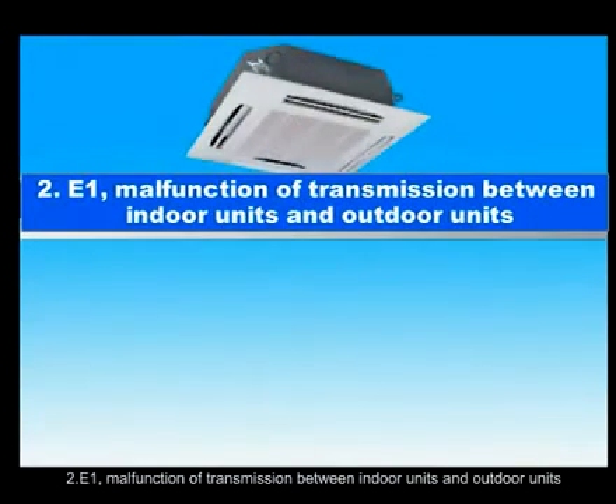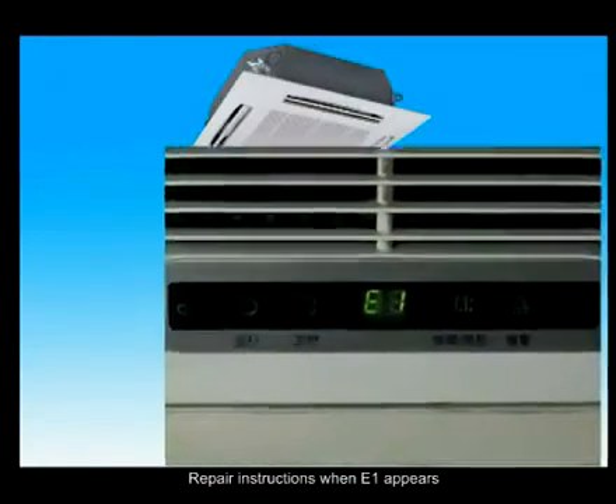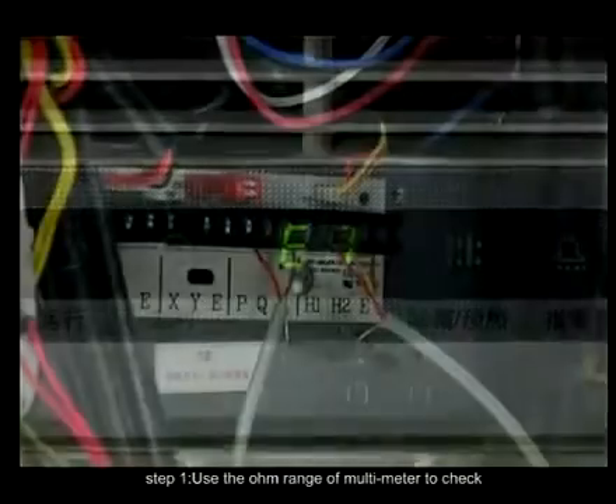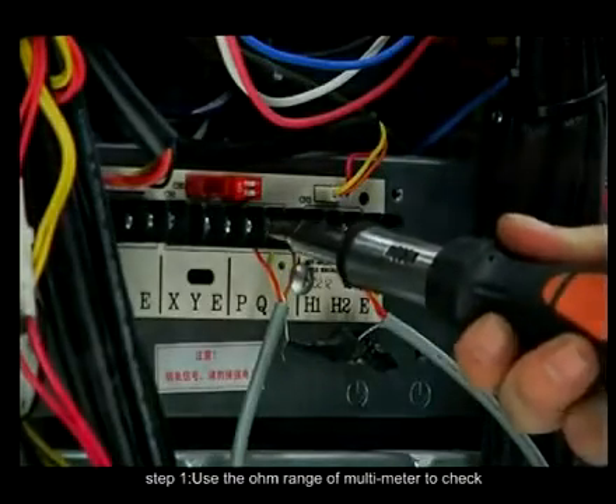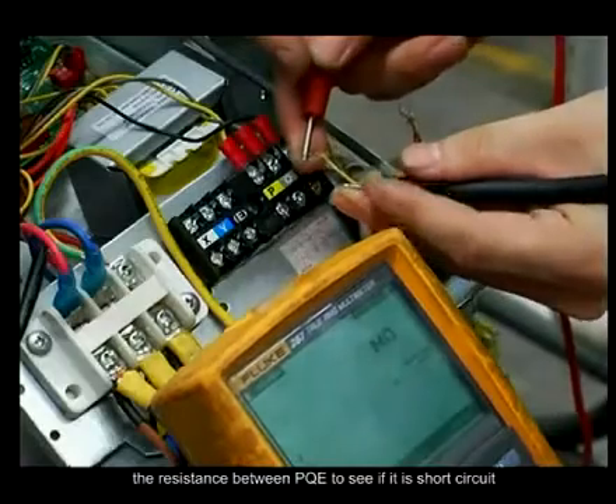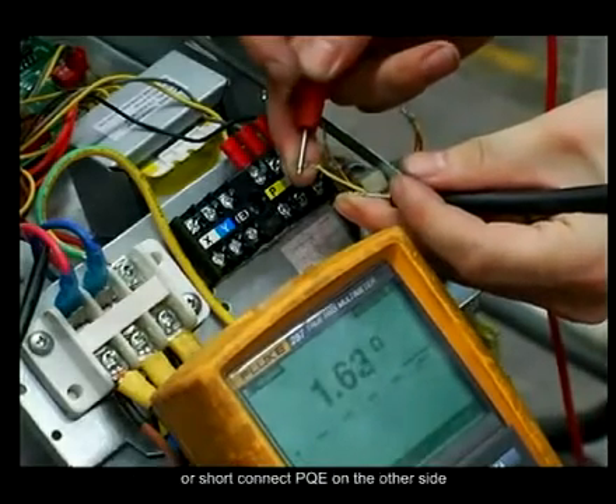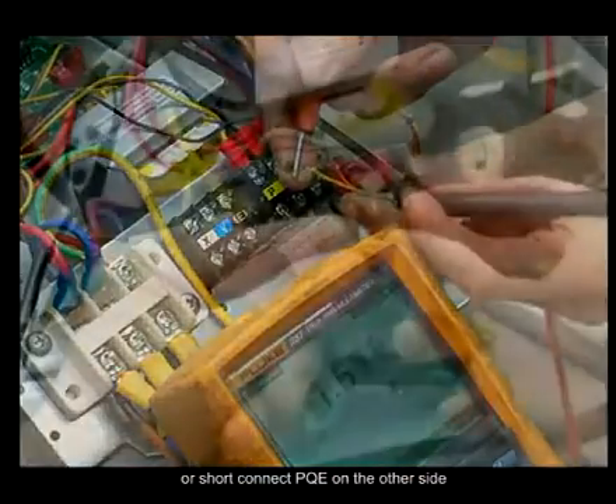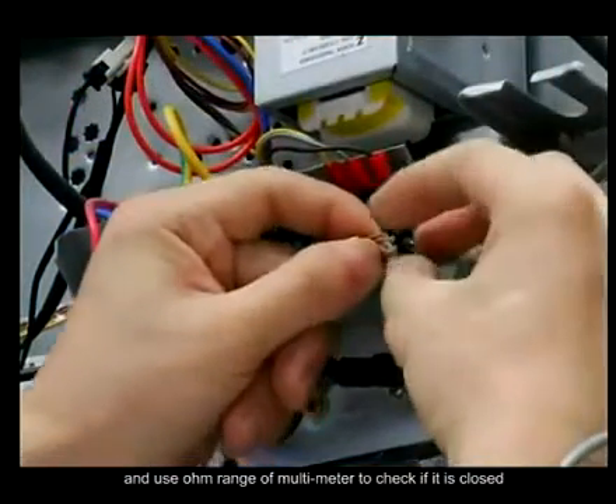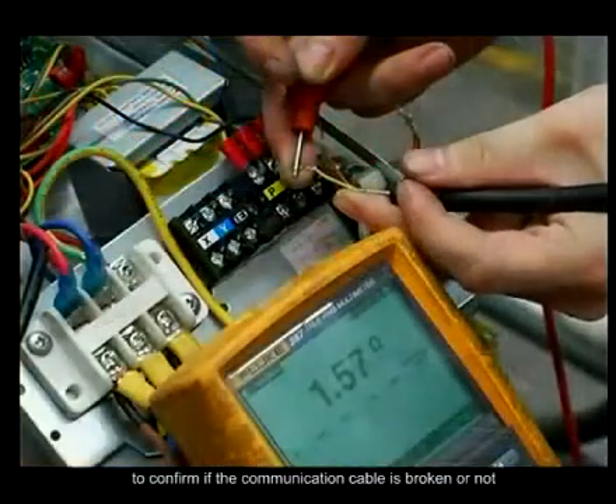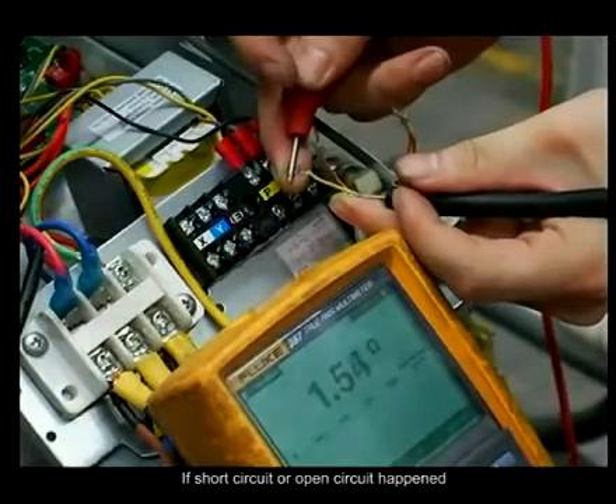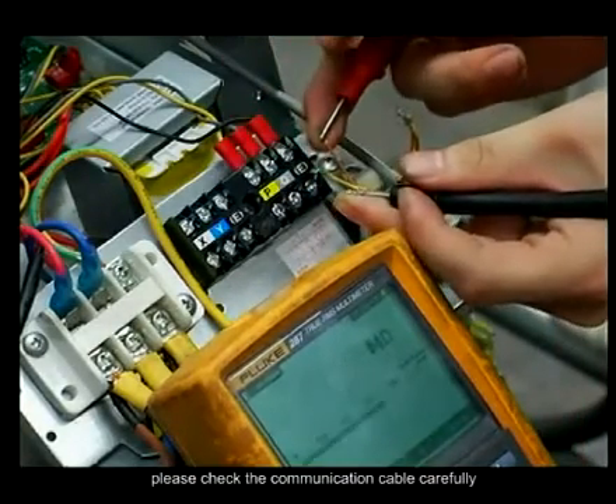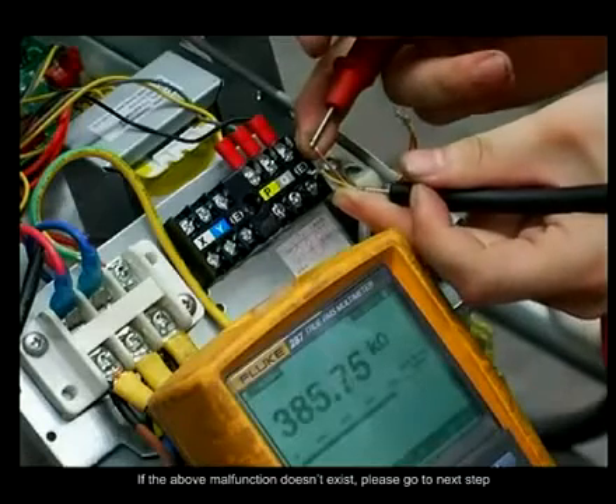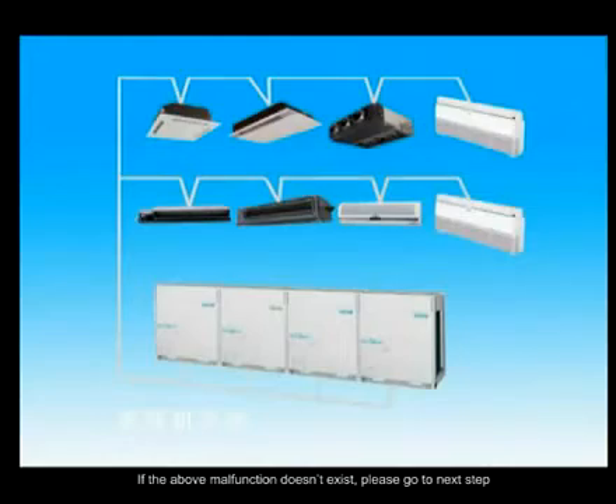2. E1, malfunction of transmission between indoor units and outdoor units. Repair instructions when E1 appears. Step 1. Use the OHM range of a multimeter to check the resistance between PQE to see if it is a short circuit, or short connect PQE on the other side and use the OHM range of the multimeter to check if it is closed, to confirm if the communication cable is broken or not. If a short circuit or open circuit happened, please check the communication cable carefully. If the above malfunction doesn't exist, please go to the next step.